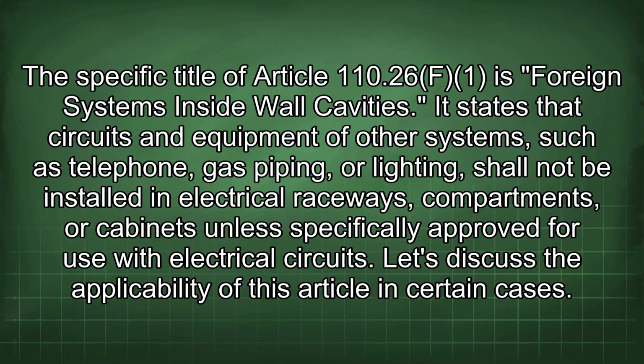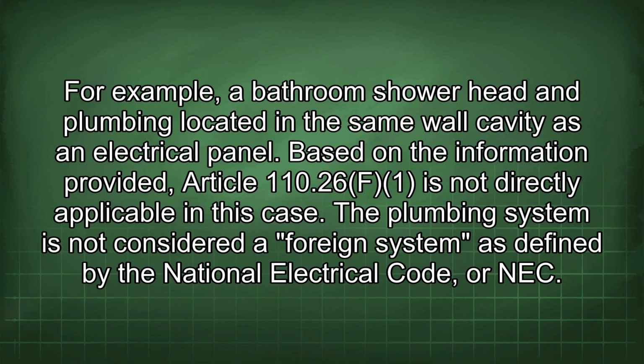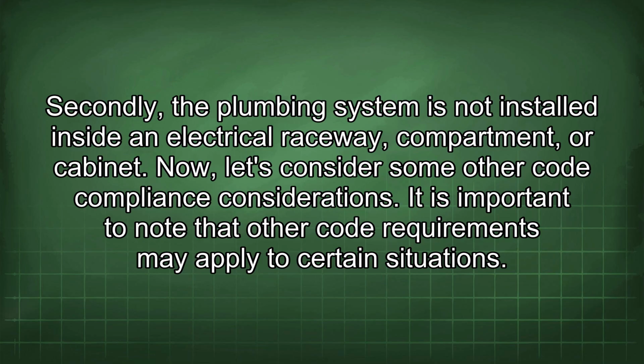Let's discuss the applicability of this article in certain cases. For example, a bathroom shower head and plumbing located in the same wall cavity as an electrical panel. Based on the information provided, Article 110.26(F)(1) is not directly applicable in this case. The plumbing system is not considered a foreign system as defined by the National Electrical Code, or NEC. Secondly, the plumbing system is not installed inside an electrical raceway, compartment, or cabinet.